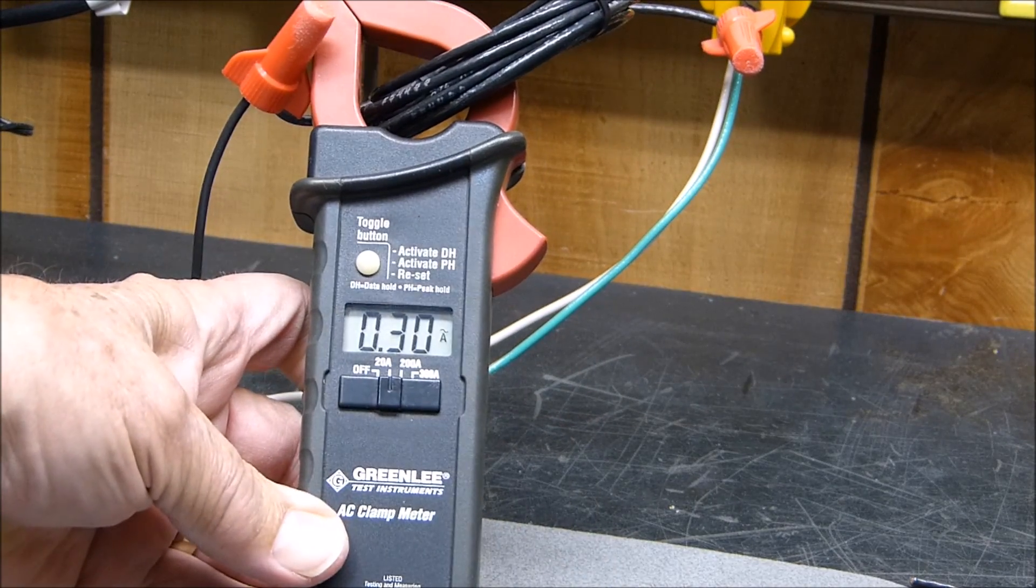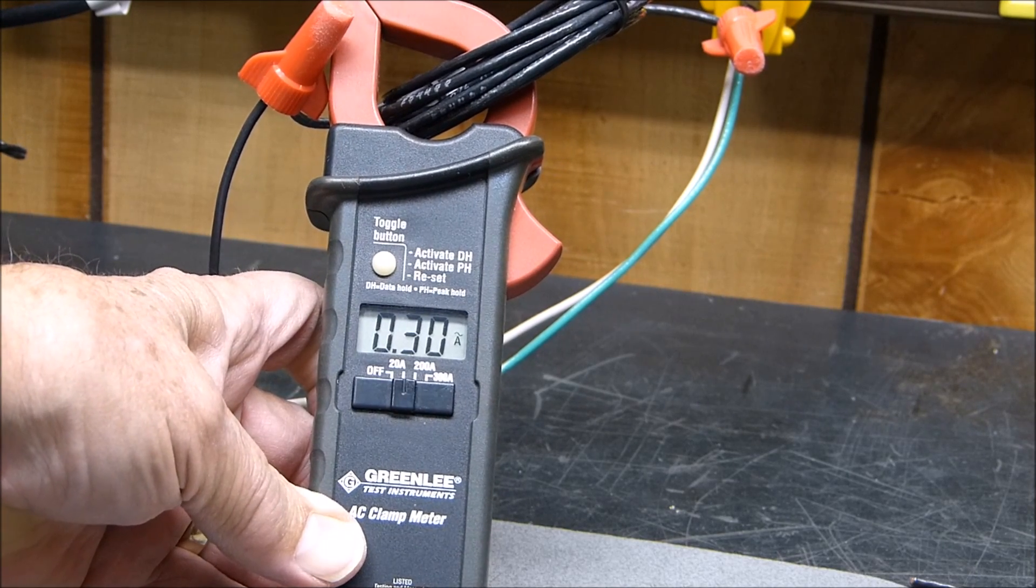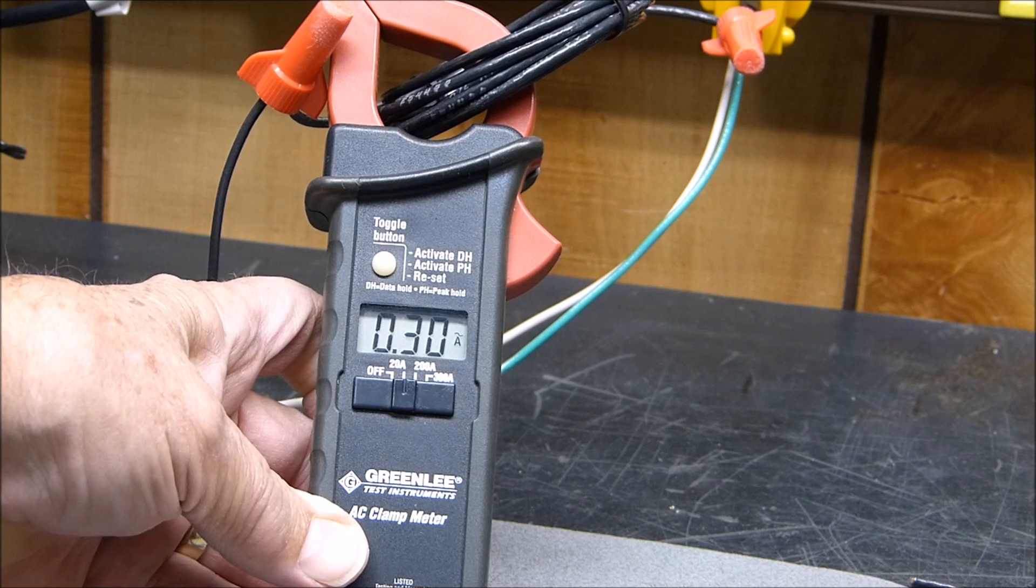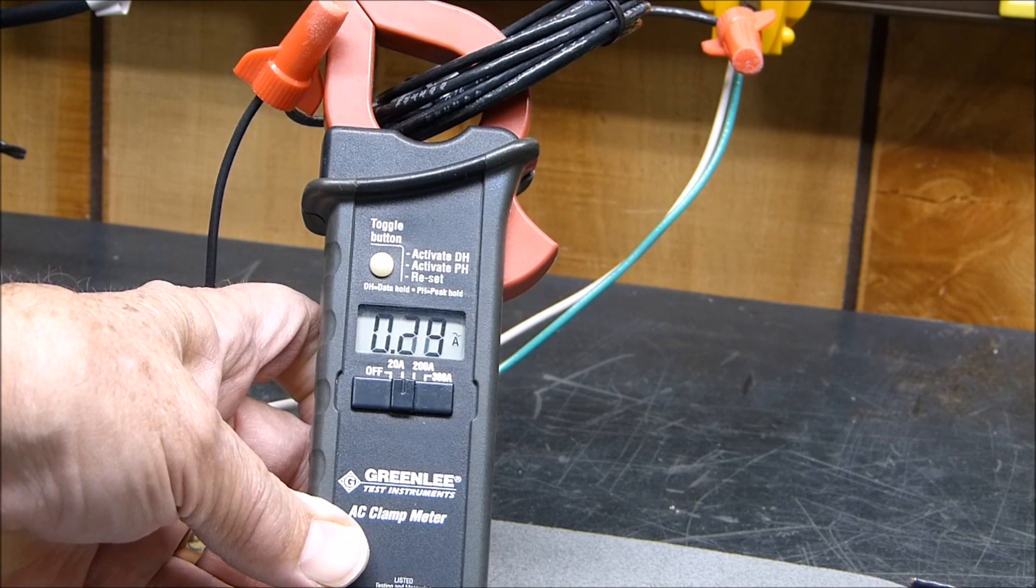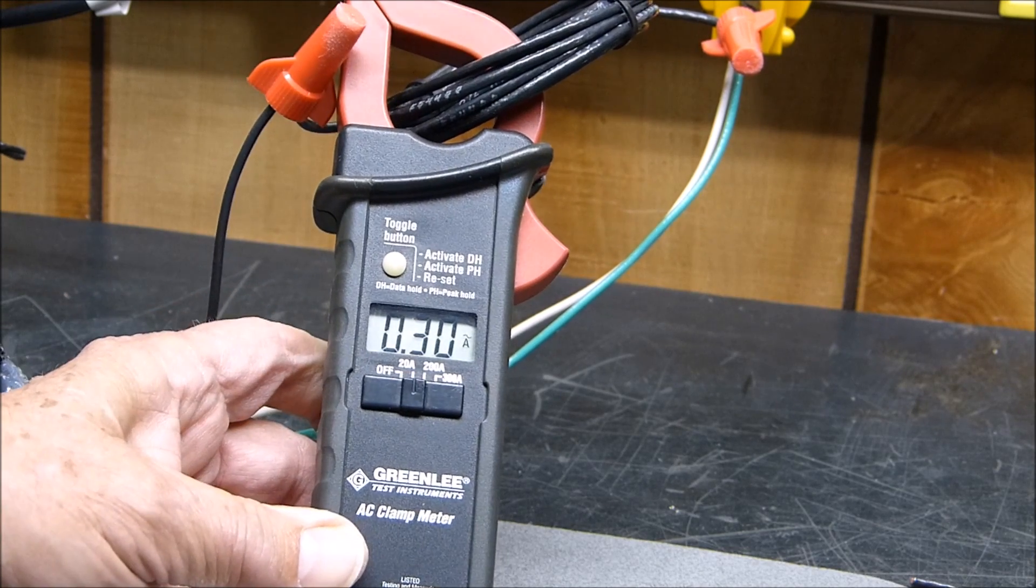But this is just simply ten turns. I mean, there's absolutely nothing fancy about it. When I clamp it around there, now it says it's 31 or 30. Now you got to know that you're multiplying it times 10. It's not really 0.3 amps. It's 0.03 amps, but it actually is 30 milliamps. So you can measure really low power stuff.